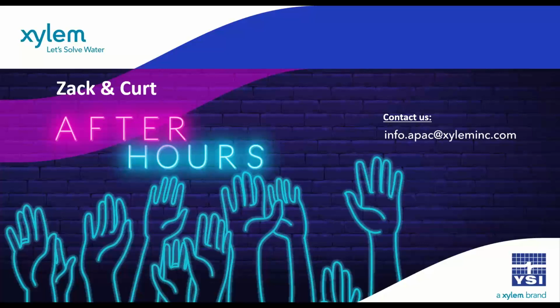Terrific, thanks, Curt. The next question concerns Pro Plus and Pro Quattro sensors. How do you mitigate pH sensor drift with every calibration? And just a special note that the units are being used mostly in seawater. Yeah, all I would say there is just with respect to storage: when you're not using the sensor, the best way to preserve the sensor, I guess, is to store it in its storage solution. I believe those sensors ship in a storage bottle that seals around the sensor, and keeping that sensor tip in its proper storage solution is a great way to preserve that sensor. If you run out of the storage solution or if it spills, I believe you can use the pH 4 buffer solution as a good substitute. Is that correct, Curt? Yes, it is.